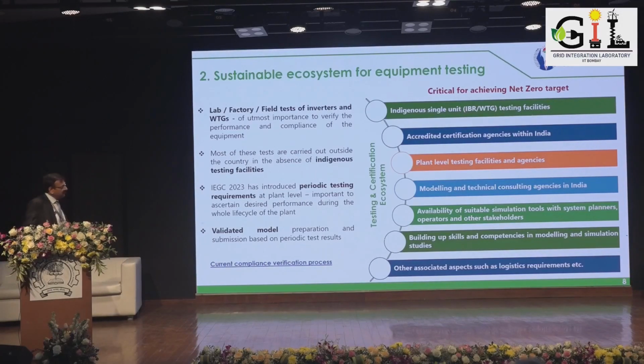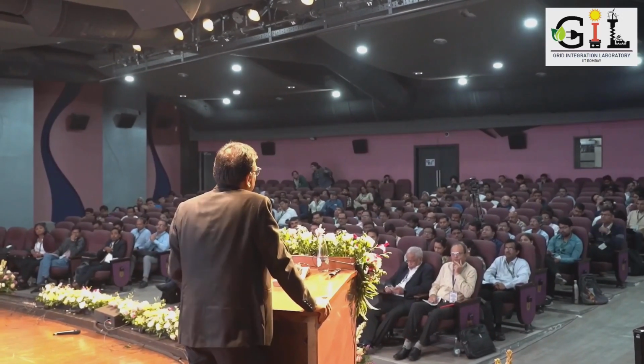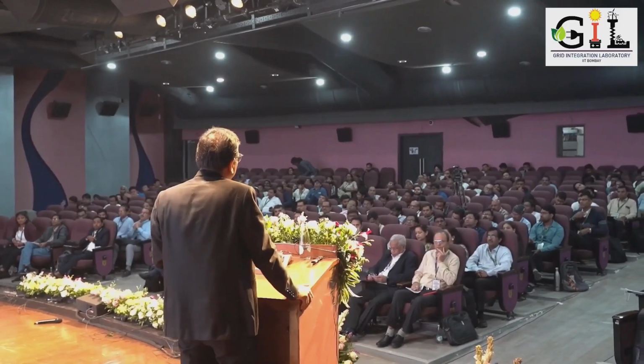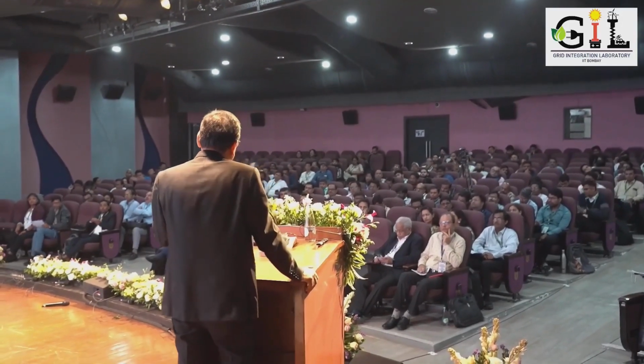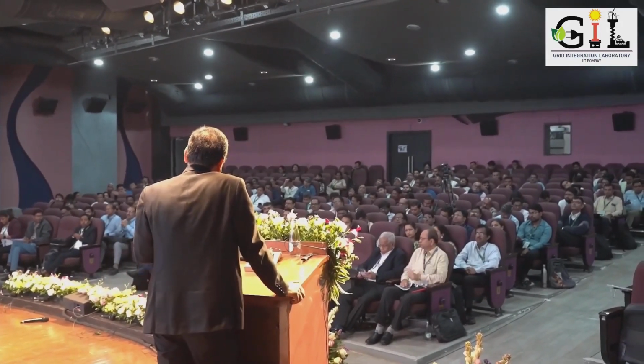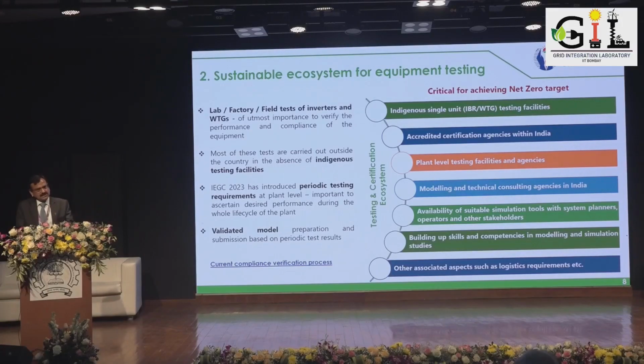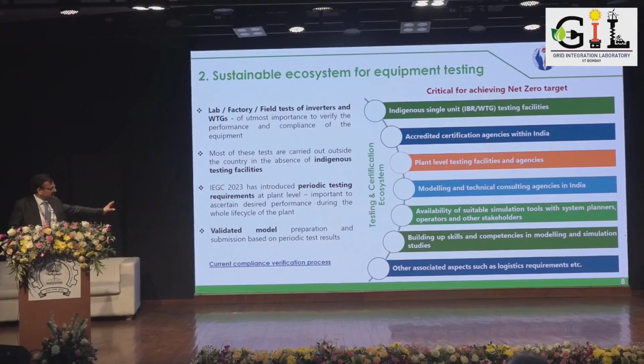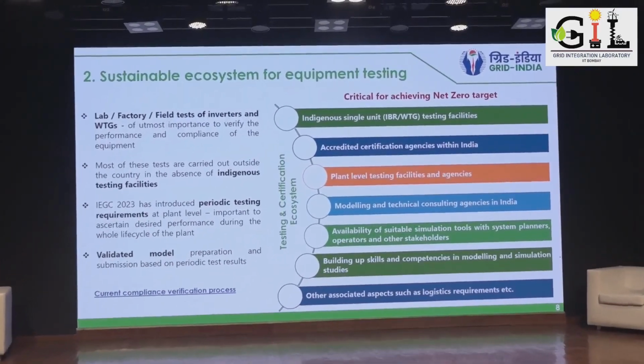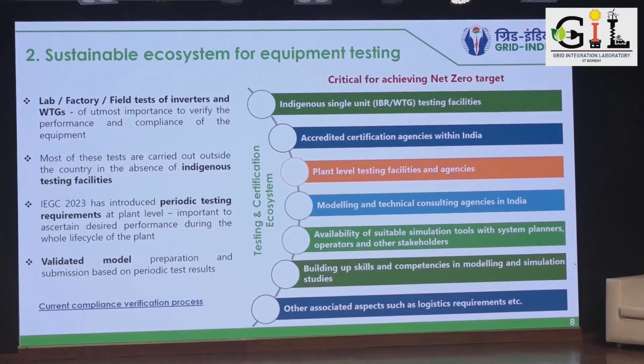Validated model preparation is important when we do field level testing, because sometimes a submitted model looks fine in simulation—LVRT, HVRT all appear correct, reaching 90% of pre-fault megawatt value within 1 second after fault clearance as the regulation says—but a number of plants have not been able to achieve that in actual operation, even though the simulation showed they were reaching that level. So there have been difficulties and issues in practice.